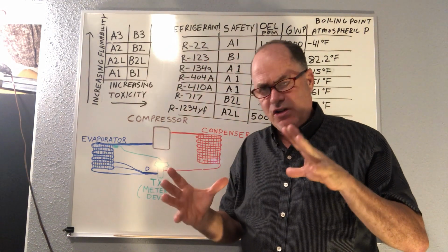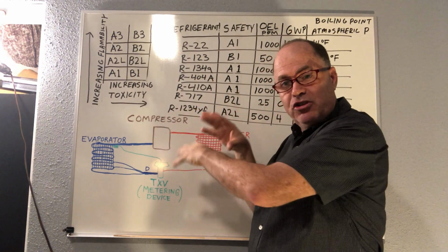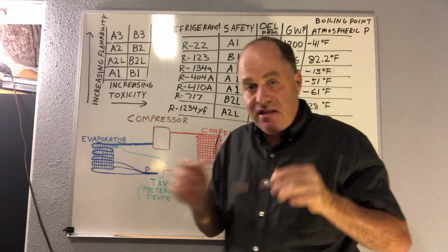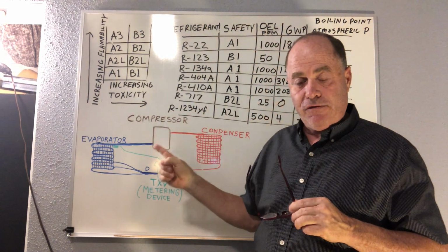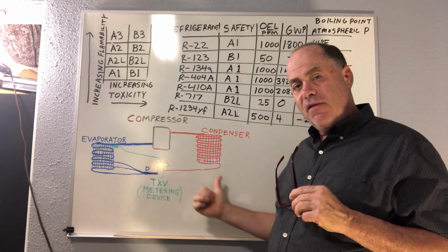Now, if you have a separate receiver also here, not part of like a water-cooled condenser, which could be a flooded condenser, but if you have a separate receiver, and this system holds more than 100 pounds of refrigerant, not only do you need a king valve on the outlet, you need a valve on the inlet, which is known as the queen valve.